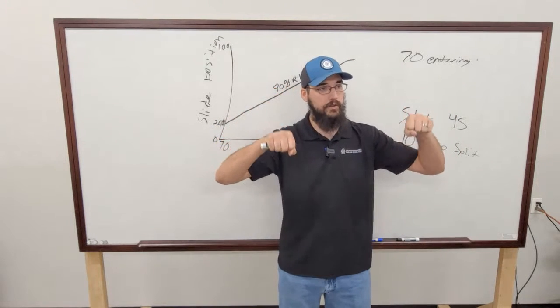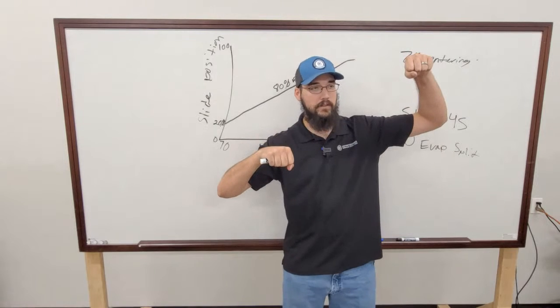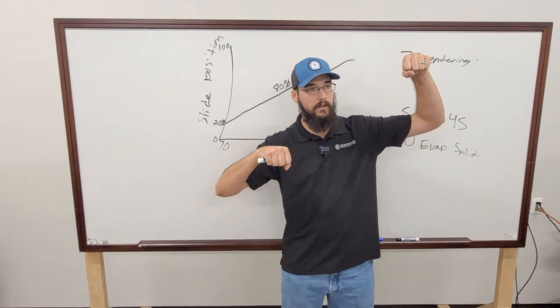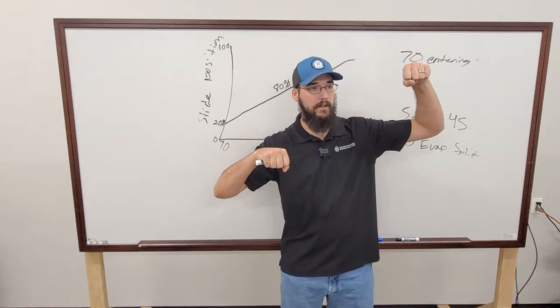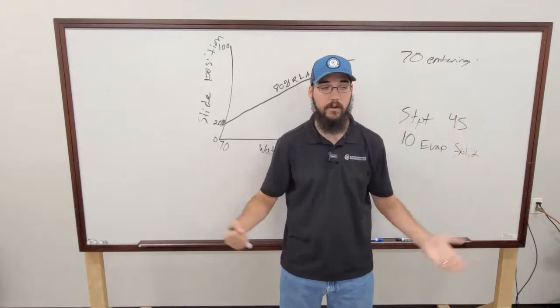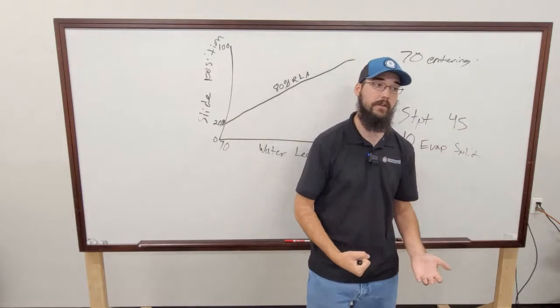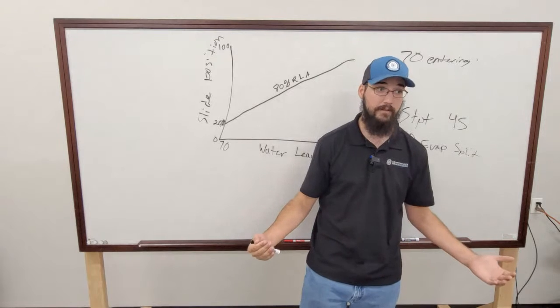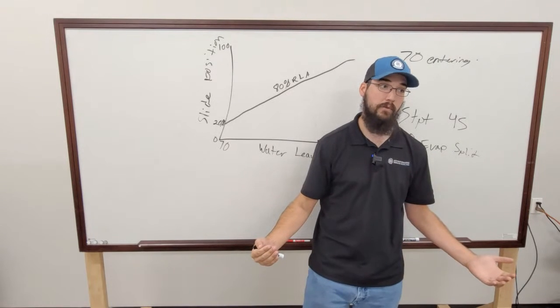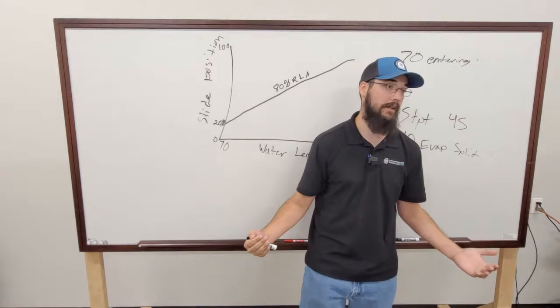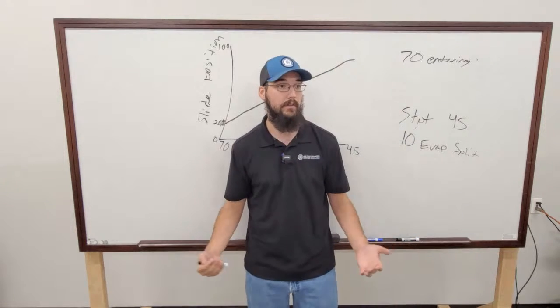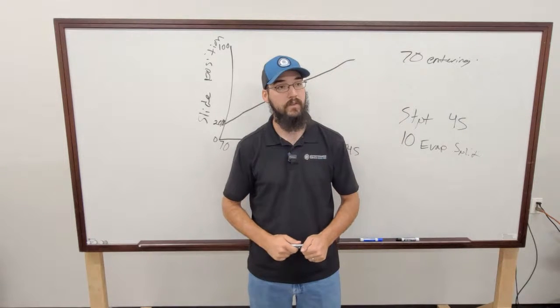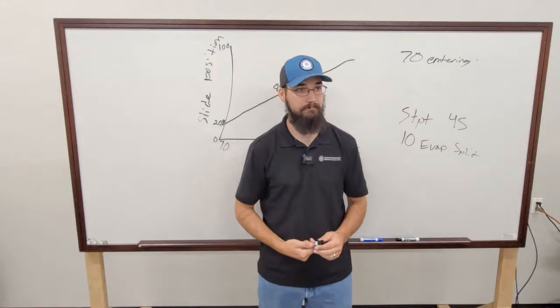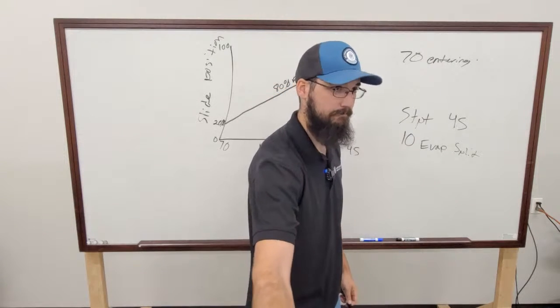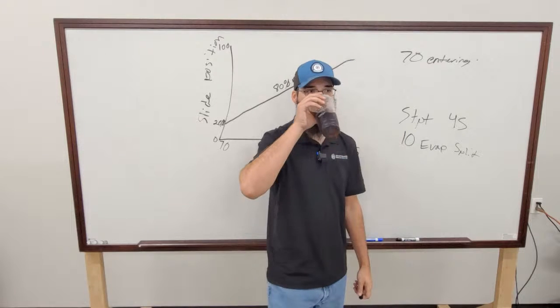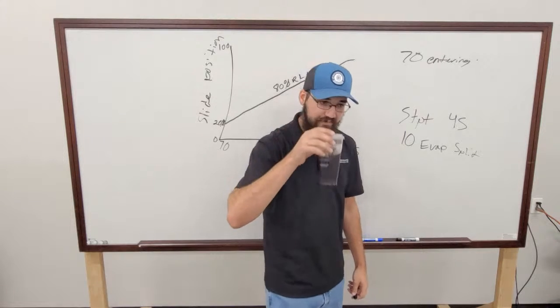In the same way, the chiller is using the exact same logic to control the individual circuits. It's going to max this one out until it sees that this one can't stabilize it. So there's a scenario where you could run over 100% RLA for an extended period of time before the chiller decides, okay, I need to bring in somebody else. That's a lot like cascading on a boiler. When you have multiple boilers, they'll cascade themselves like that. Then they'll back themselves down.